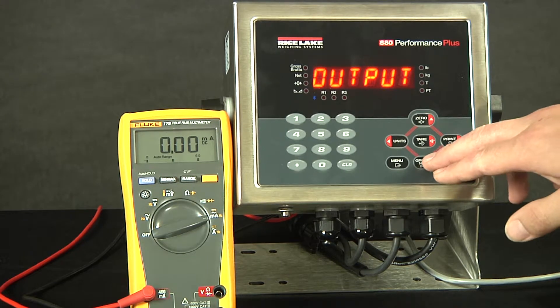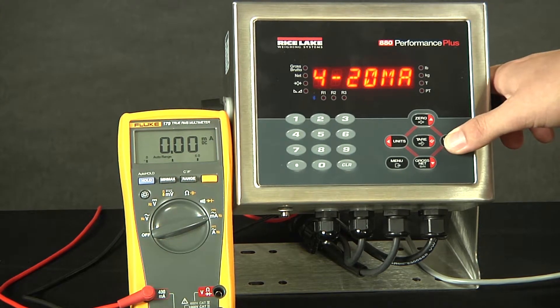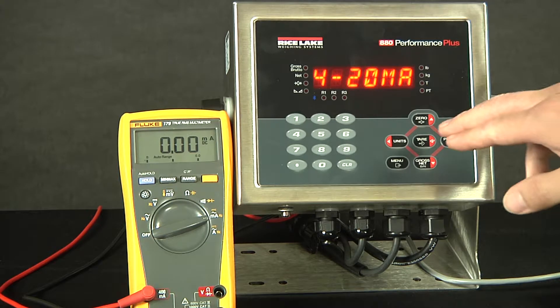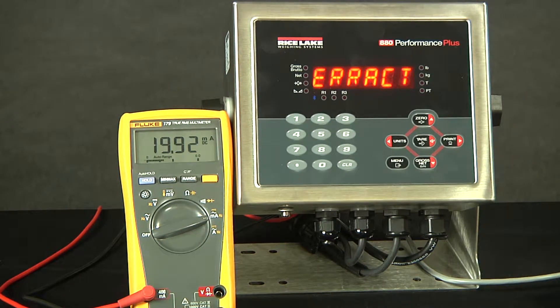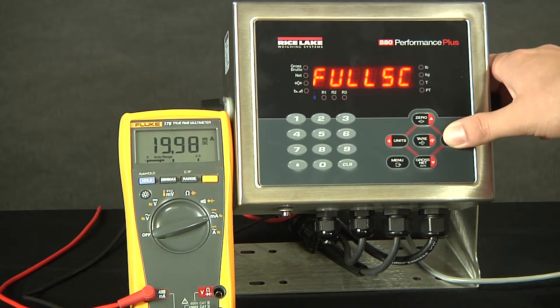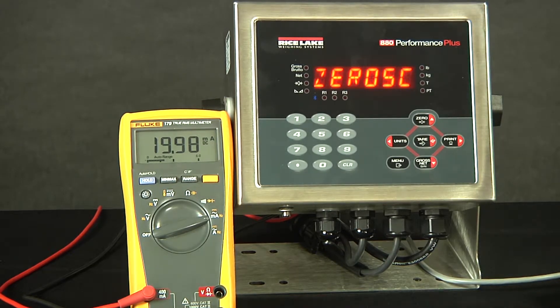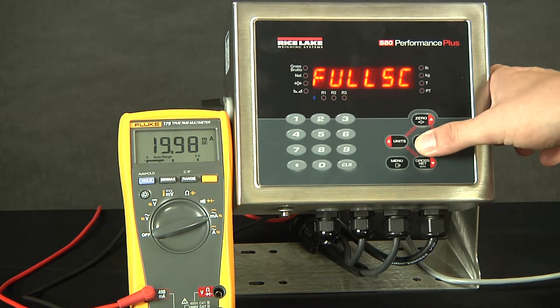Next is the output type. Here we have zero to 10 volts. For this demonstration, we will be scrolling right twice for four to 20 milliamps. As we hit enter, it is accepted. The error action indicates what the scale should do if there is an error condition. Full scale is the first selected option. There is also hold the current milliamp output or going to a zero scale milliamp output. For this demonstration, the zero scale output would be 4 milliamps and the full scale output would be 20 milliamps. We will go back and accept a full scale error.